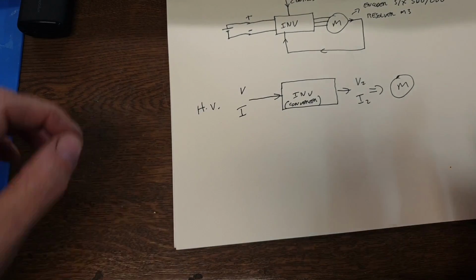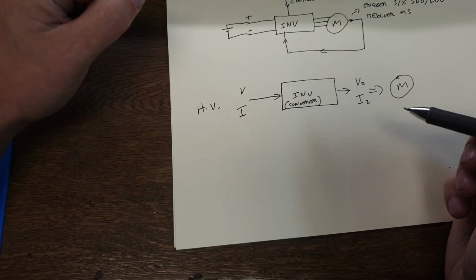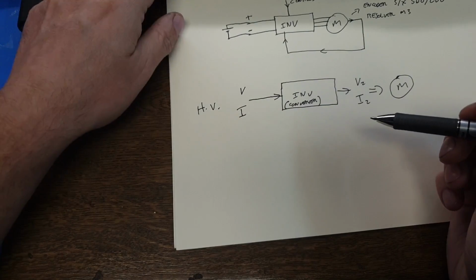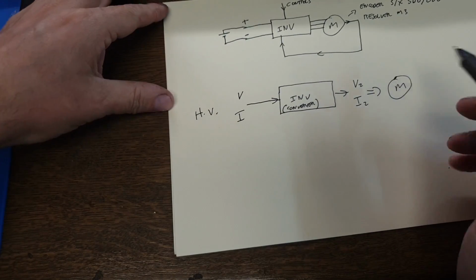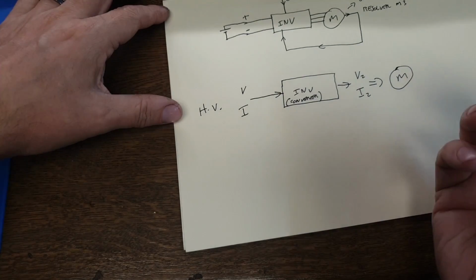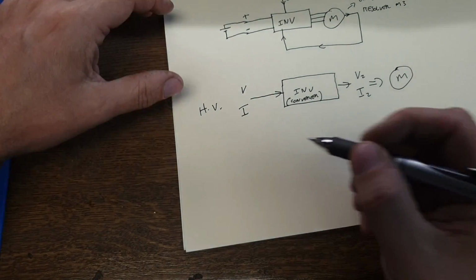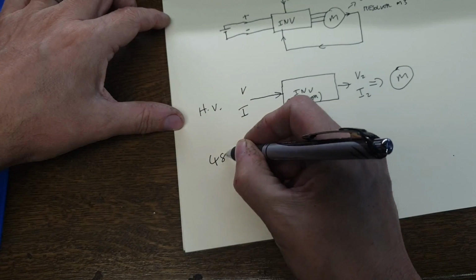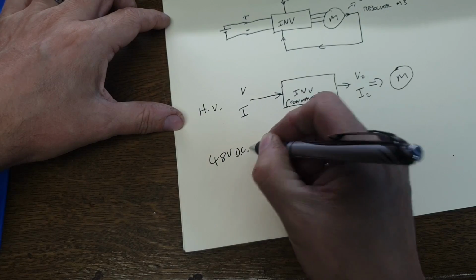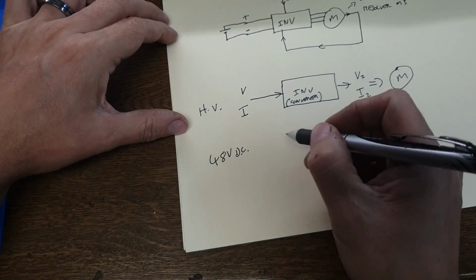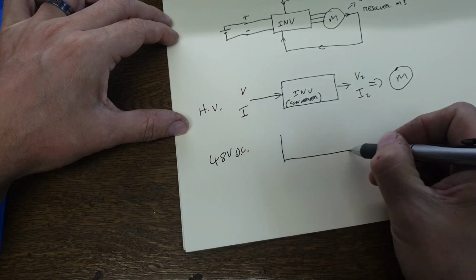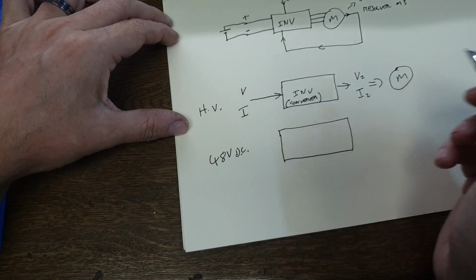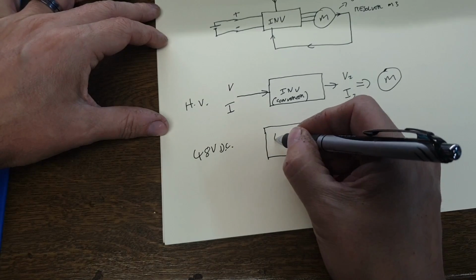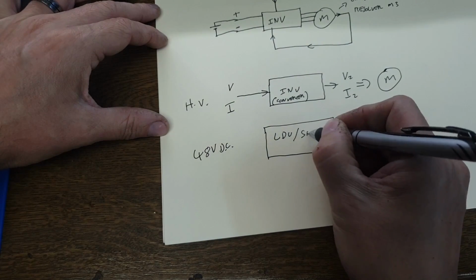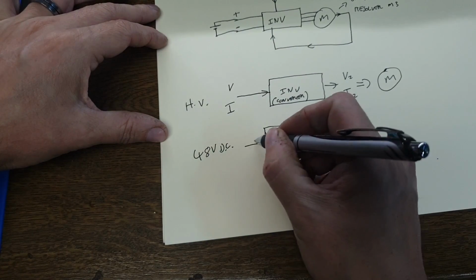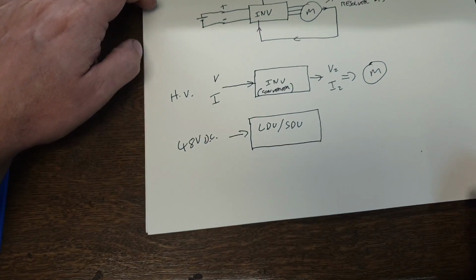Typically, what we do when we're doing the low voltage testing part is we take, usually, I'd recommend something around 48 volts DC, and we apply this to our, just call it LDU for this sake. We can say LDU, SDU. So we're going to put that into the inverter, okay?